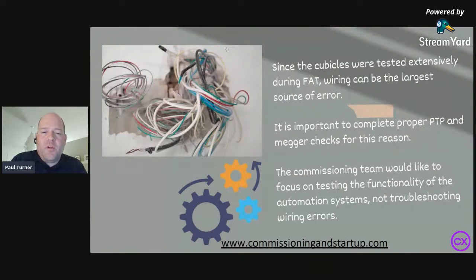So one thing that's very important as part of the construction phase is to do all the proper point-to-point checks and all the megger checks of all the cables that have been pulled, to confirm that it's been installed per drawings and that all the cubicles are interconnected as they need to be.